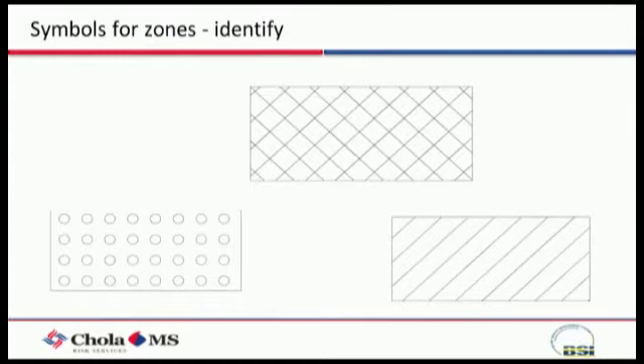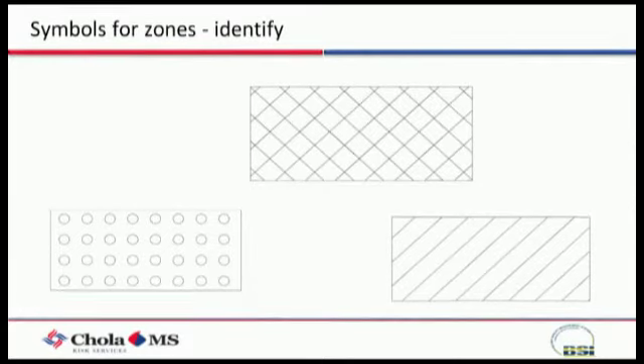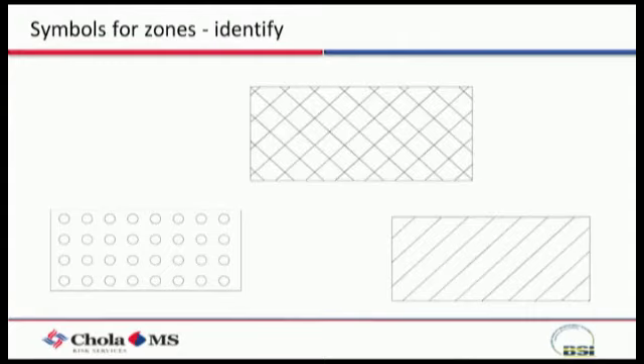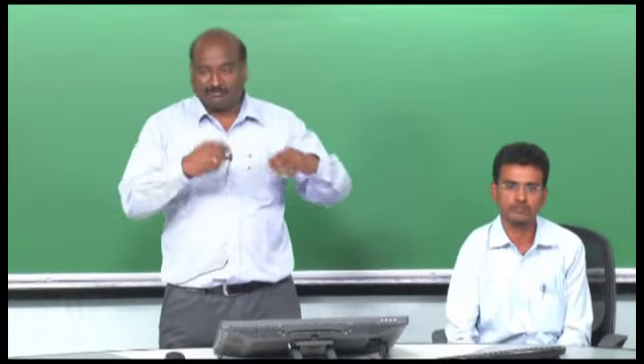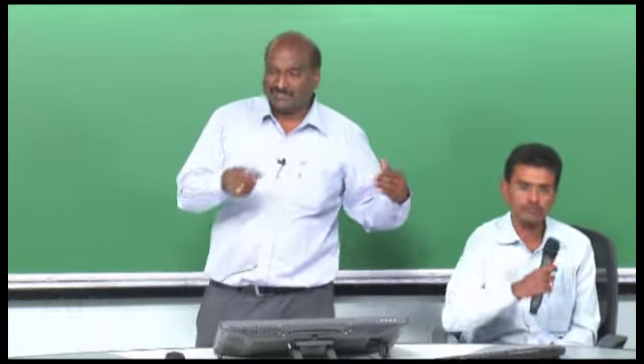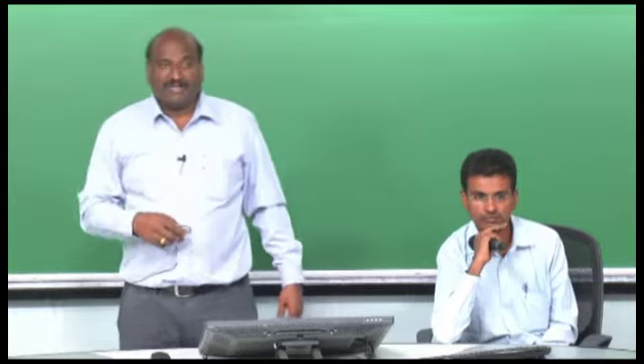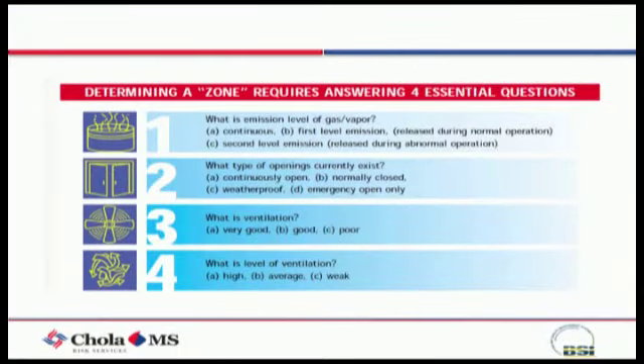In a hazardous area classification drawing, it looks like checked boxes, dots, and single and double hash marks. Based on this, you get to know which is zone 0, zone 1, or zone 2. Zone 0 normally will not be hatched in the drawing — only zone 1 and zone 2 would be hatched. There are other factors also which determine whether to classify areas as zone 0, zone 1, or zone 2 — one of which is the type of ventilation.